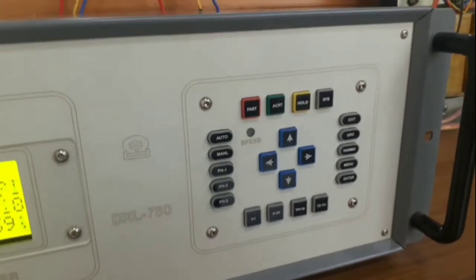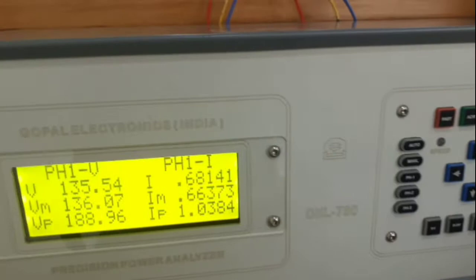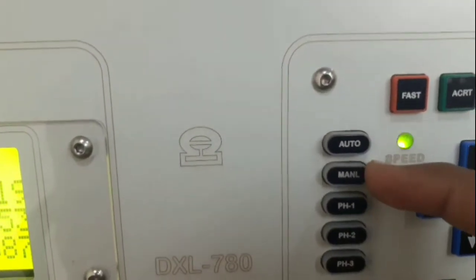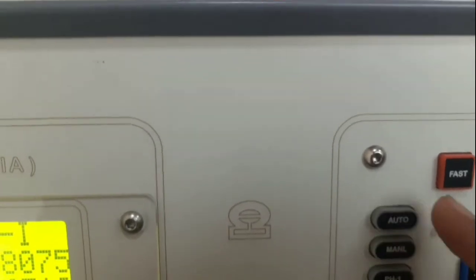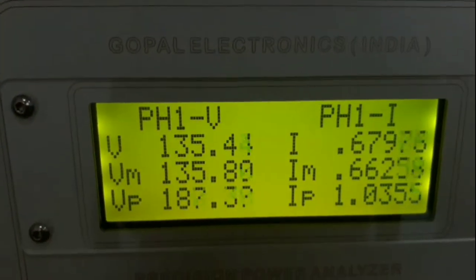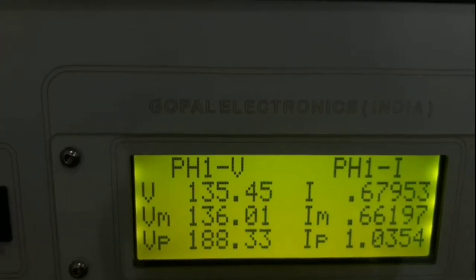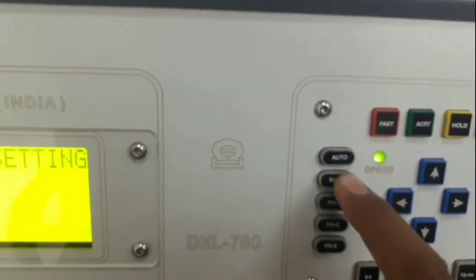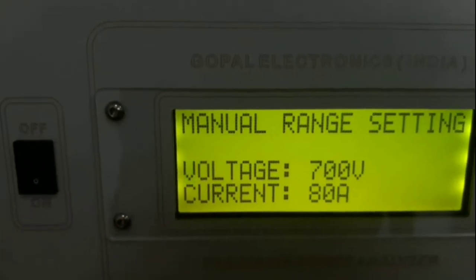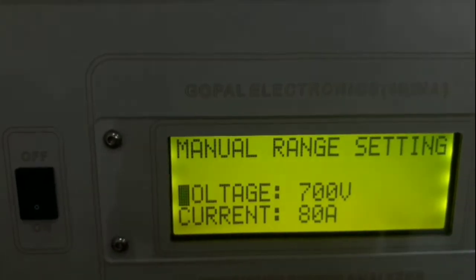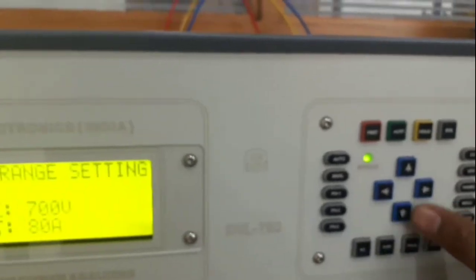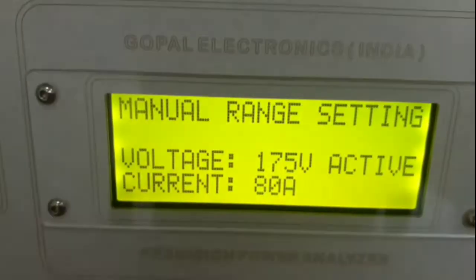As I said, this equipment is multi-range equipment. For selecting range, two modes are given, auto mode and manual mode, with an auto key and a manual key. If you want to select the range automatically, press the auto key, and the range will be selected automatically. If you want to select the range manually, press the manual key. Now you are able to enter the range value. First you can enter the range of voltage. By pressing the up down key, you can select the value, and if you want to enter 175 volt, then press enter. Now it will be activated.